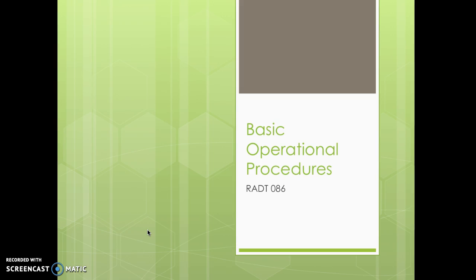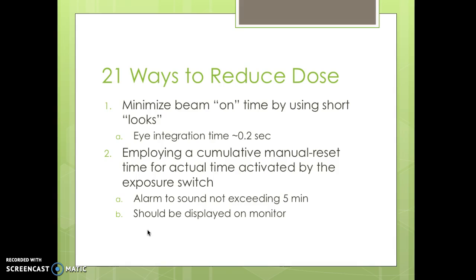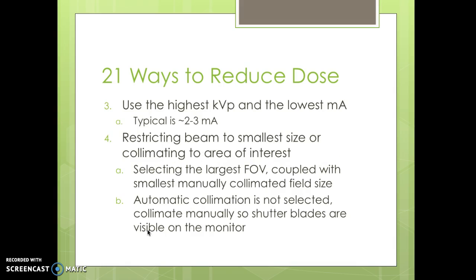Basic operation procedures — the goal is to reduce radiation. Operators of fluoroscopic equipment must reduce unnecessary radiation dose to the patient, themselves, and others. There are 21 ways to reduce dose. First, minimize beam-on time by using short looks — the eye integration time is about 0.2 seconds so you can do quick looks. Employ a cumulative manual reset timer not exceeding 5 minutes, displayed on the monitor. Use the highest kVp and lowest mA — typical is 2 to 3 mA — and restrict the beam by collimating to the area of interest.